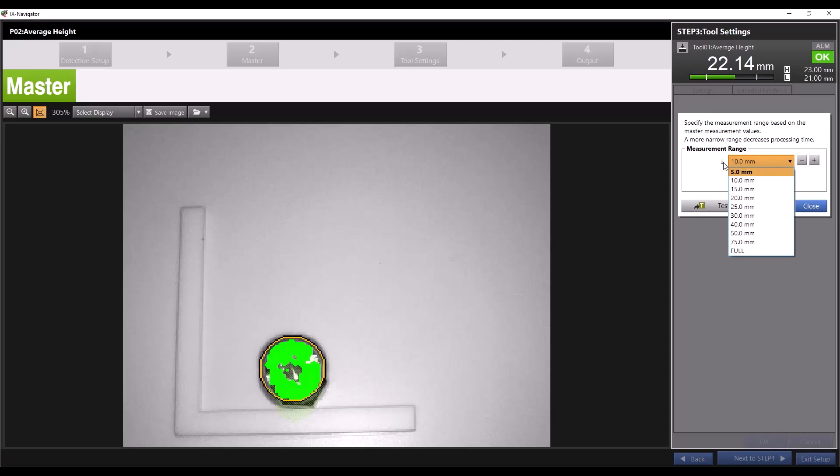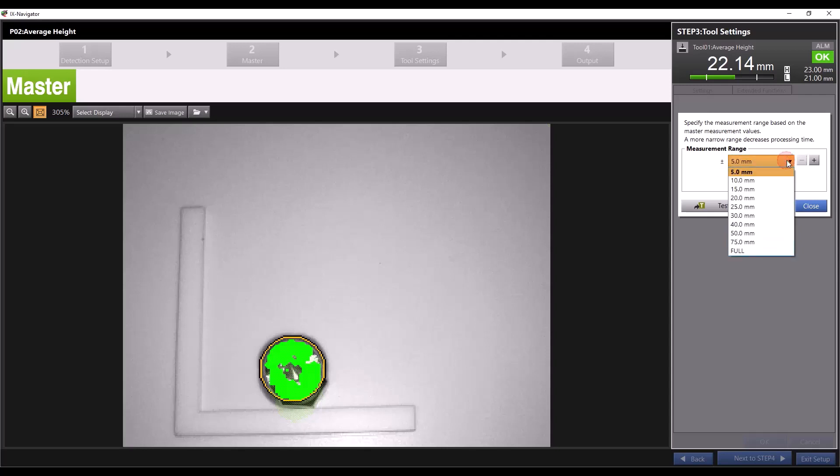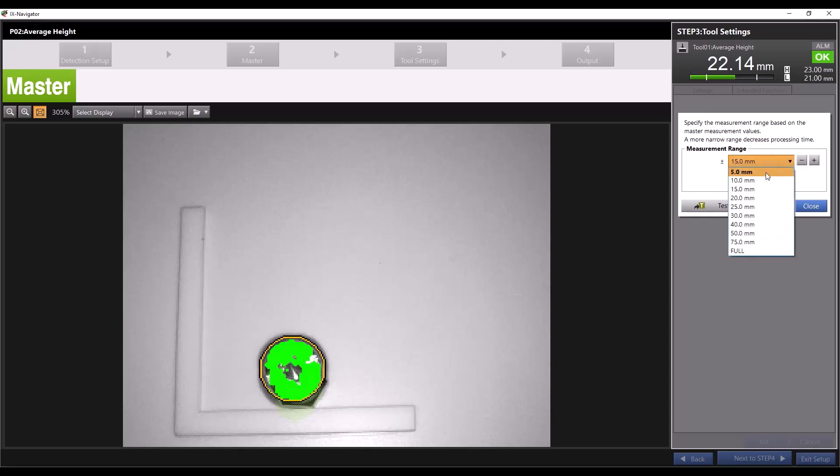if you want the iX to ignore any values outside of plus or minus 5 millimeters from the measured point you can set the range to plus or minus 5 millimeters. You can see visually what areas are excluded for each point as you change your range by observing the overlay on screen. We'll leave our range at the default then click close.